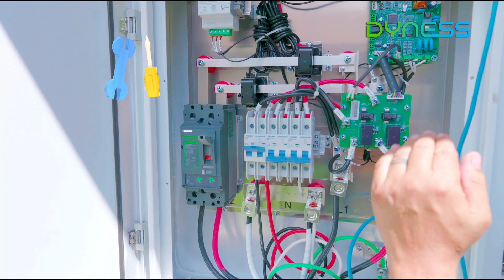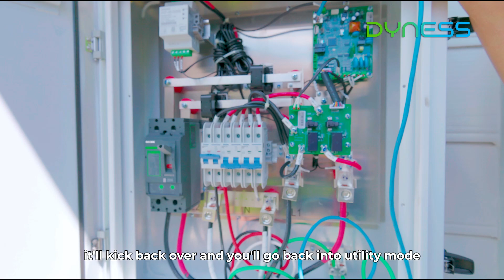And transfer and have the utility in the open position, meaning not having utility power, once lost, to backup power. Once it's in backup power, it'll stay maintained until the utility is maintained and on. It will see the frequencies and the hertz, maintain the sine wave, and once it's all established, it'll kick back over and you'll go back into utility mode.